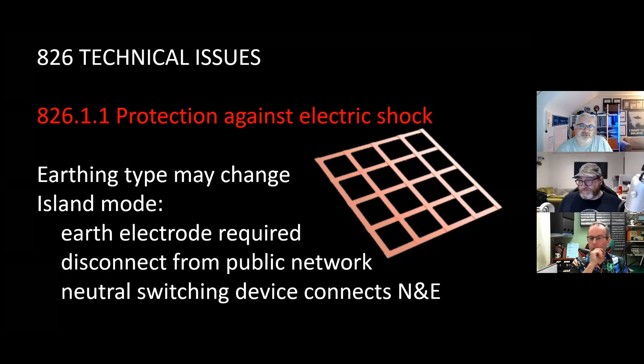So you could go from having one earthing system to a completely different one and then back again, several times a day. So this follows on from that. We've got earth fault current in different systems, so TN, TT, or even IT, because that is a valid operating or actual earth system. I have a feeling IT systems are going to come back quite readily, especially if they're removing RCDs, or enforcing RCDs - what's your alternative?